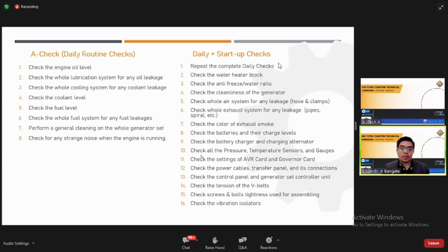Check all the pressure and temperature sensors and gauges. Check the settings of the AVR card and governor card. Check the power cable, transfer panel and its connections. Check the control panel and generator set control unit. Check the tension of the V-belts. Check the screws and bolts tightness for assembling and check the vibration isolators. Sometimes this is not noticed until the generator starts shaking, because our vibration isolators are sometimes hidden, the rubber.